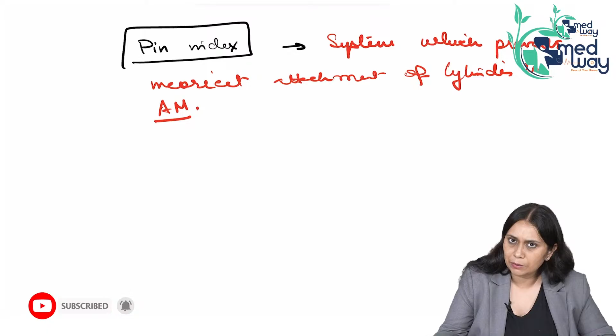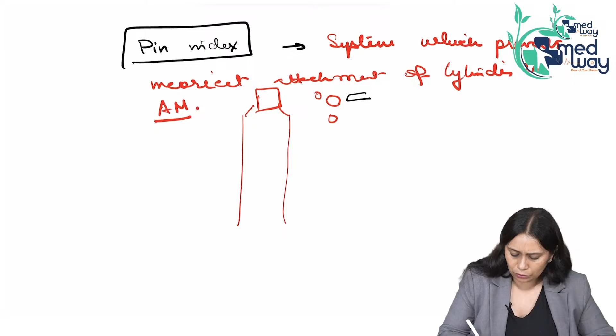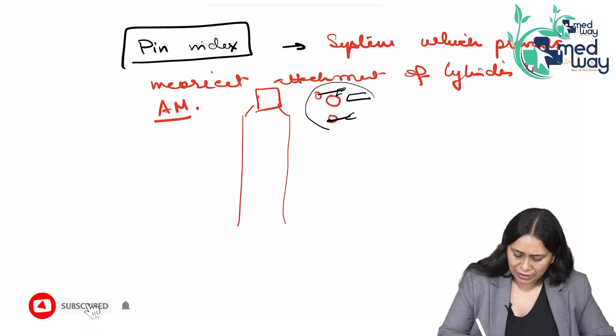Now, let's say this is the cylinder, this is the shoulder and this is the valve of the cylinder. On the valve of the cylinder, there is an opening called port, from which the gas will enter from cylinder into the machine. This goes into the nipple coming out from the anesthesia machine. Below the port, there are two holes present at fixed positions to go into pins coming out below the nipple of the anesthesia machine. So, the pins go inside the pinholes, and the arrangement will be very specific for a particular gas. This system will prevent incorrect attachment of cylinder to machine. If I try to attach another gas cylinder at a place meant for some other gas, it will not fit. So, we need to know about the pin index.